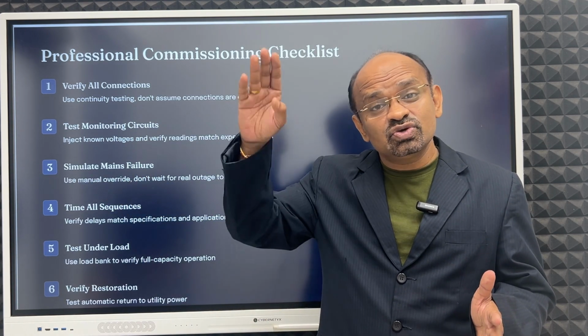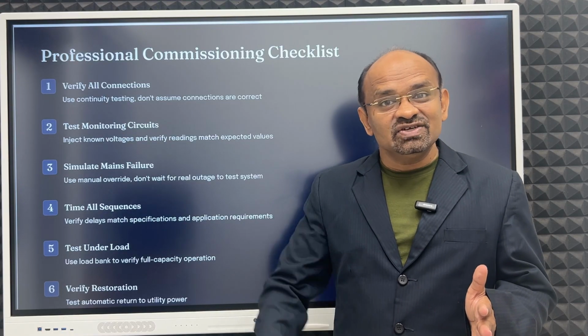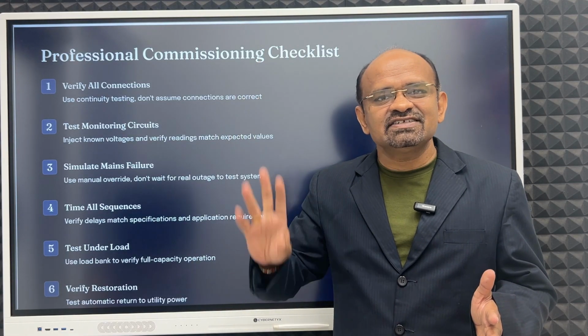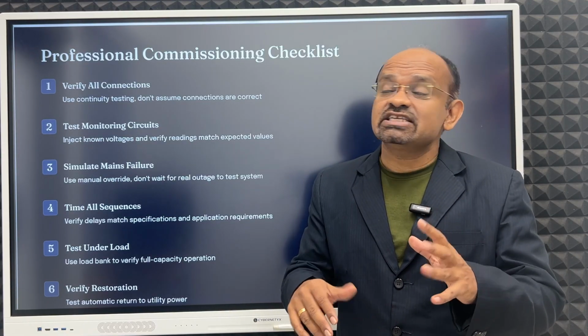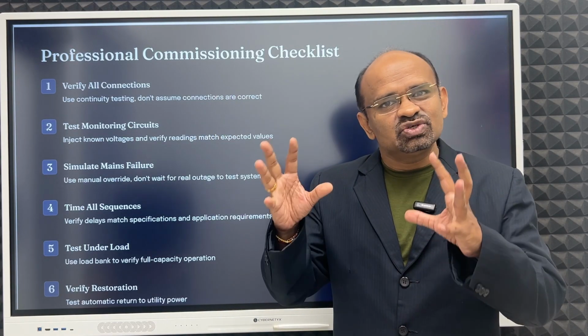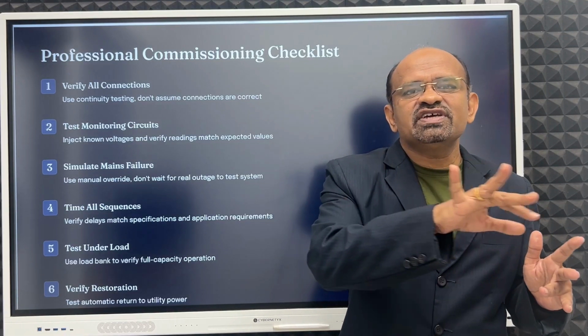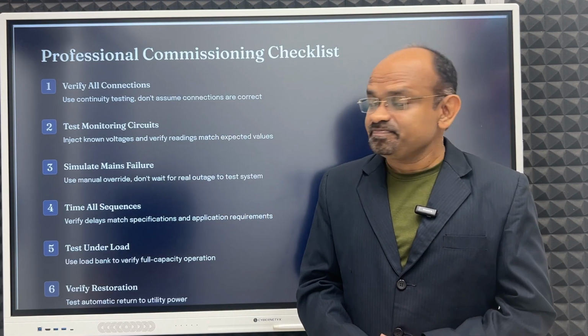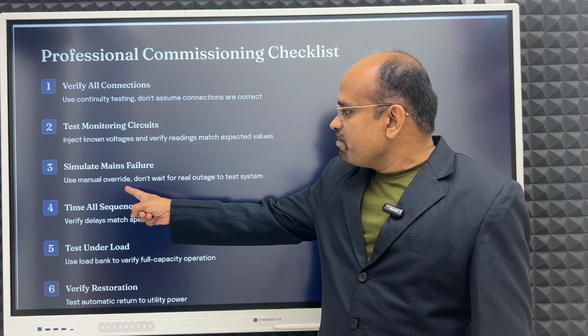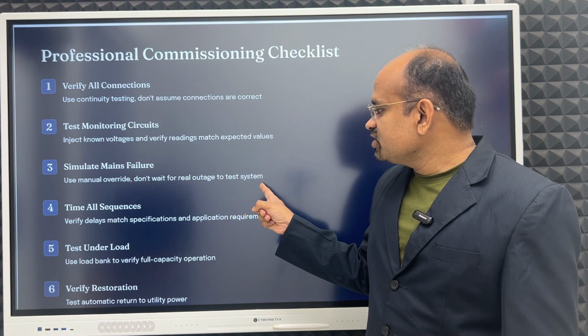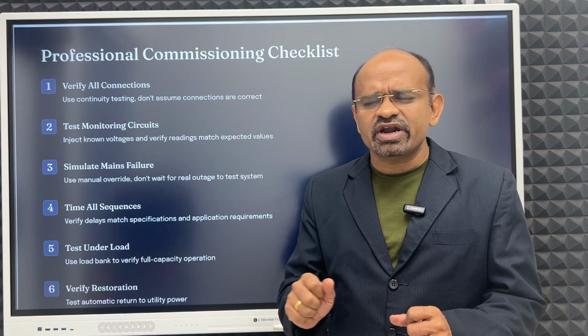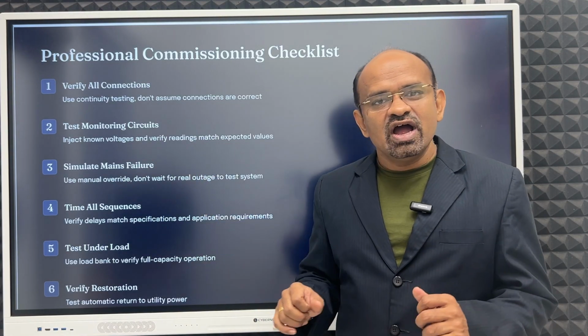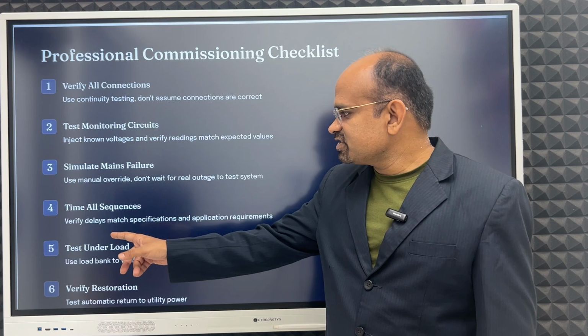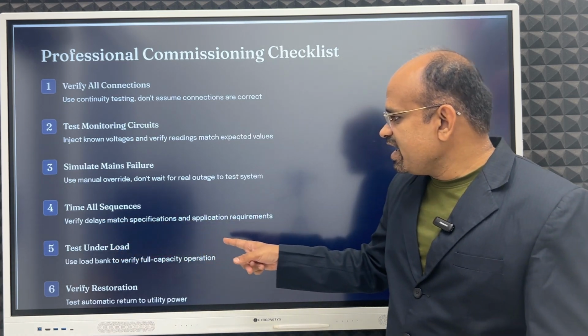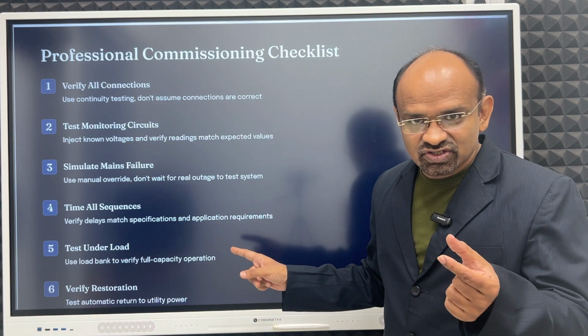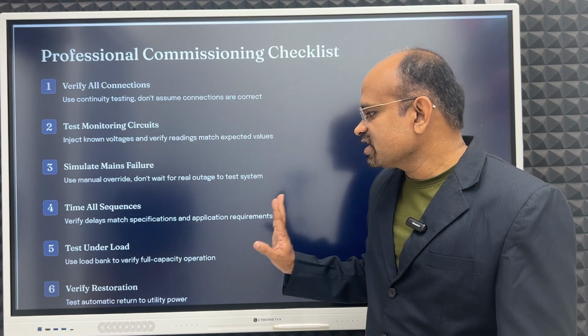Mains you should simulate; you should fail it and then start the mains, fail and start. Then it should act accordingly as per our time settings. It should take the delays, and the whole sequence should happen as desired. So use manual override; don't wait for a real outage to test the system. Just use manual override from auto and test it for the simulation. Time all sequences, verify delays match specifications. Every delay you should match to the application's requirement.